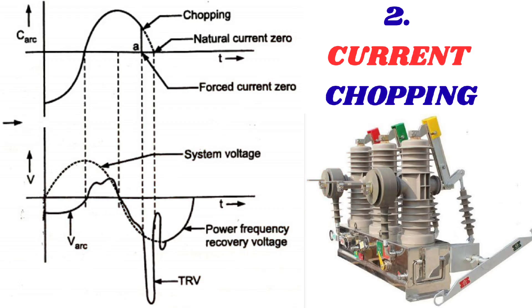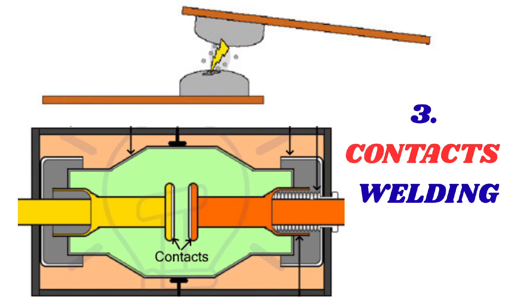Second, current chopping: VCBs can experience current chopping, which occurs when the circuit breaker interrupts the current before it reaches zero. This can cause voltage spikes which can be detrimental to equipment and potentially lead to insulation failure. Current chopping is more likely in applications with high fault currents or inductive loads. Third, contact welding: VCBs can experience contact welding, which occurs when the contacts fuse together due to high currents or arcing, potentially leading to equipment damage. To mitigate contact welding, VCBs are designed with specialized contact materials and geometries.